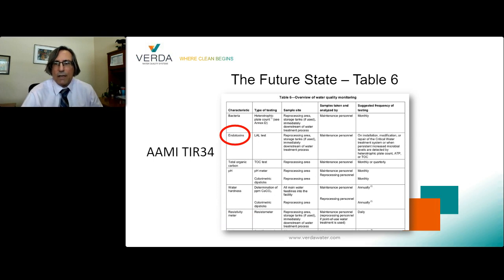It is typical to have what's called UV filtration, which is a device that critical water in the loop passes through and is subject to ultraviolet radiation. This destroys pathogens, but the byproducts of destroying pathogens can be endotoxins. Without an intact endotoxin filter, they are going straight to your instruments when you perform final rinse.